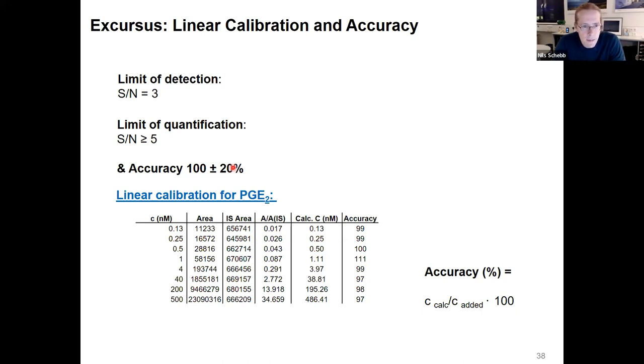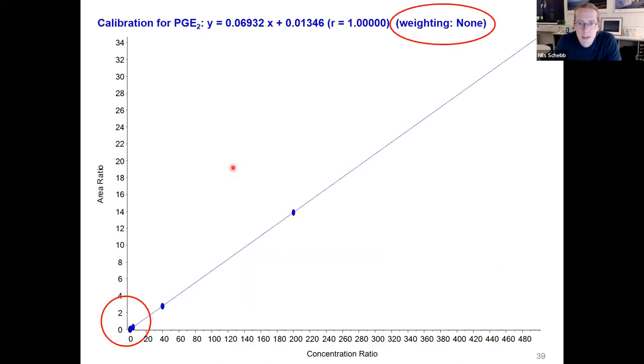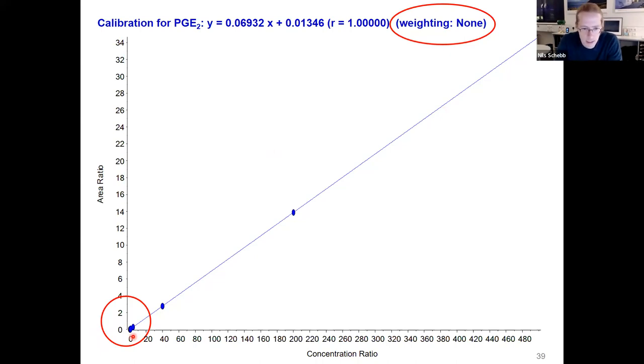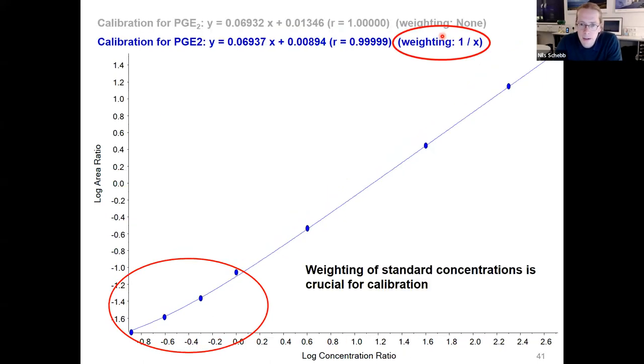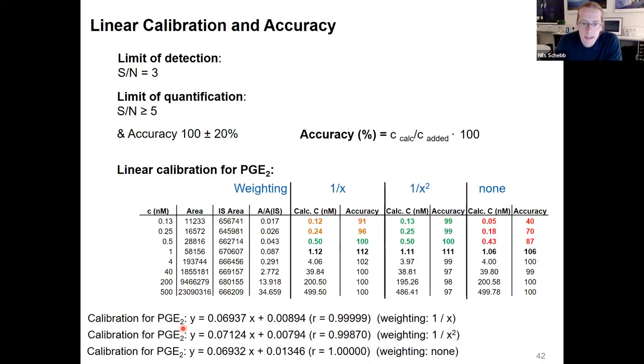This is rarely presented in biological methods. Instead, people sometimes show their R or R-squared value and seem proud of a value of 0.9999 — but this actually says nothing. If you have a standard calibration line plotted on a linear scale, you don't see what happens at low concentrations, which are typically of interest. It's better to use a log-log plot, which immediately reveals problems. In particular, for linear regression it's really important to use a weighting of 1/x or 1/x² of the concentration; otherwise, low concentrations are not well accounted for in the regression.